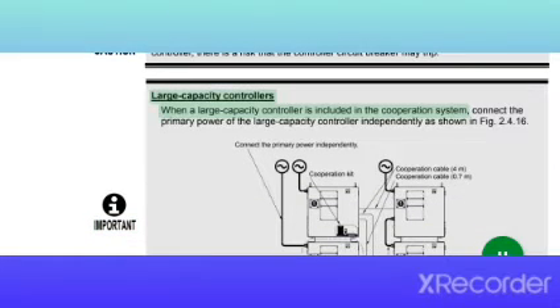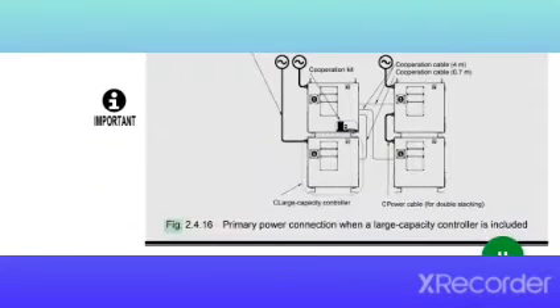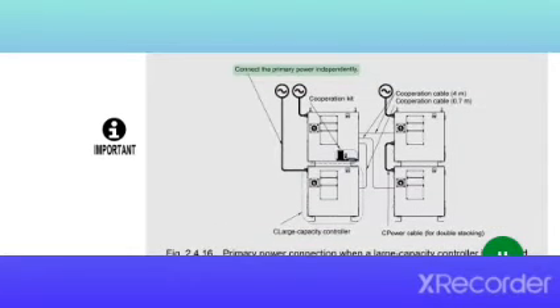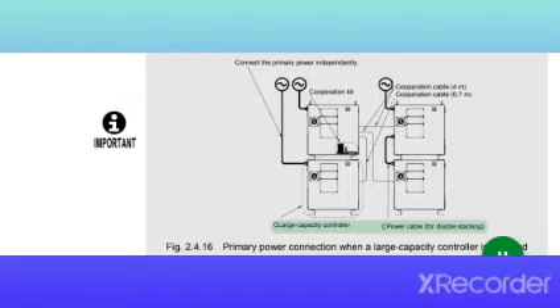Important. Large capacity controllers. When a large capacity controller is included in the cooperation system, connect the primary power of the large capacity controller independently as shown in Fig. 2.4.16. Fig. 2.4.16 Primary power connection. When a large capacity controller is included, connect the primary power independently. Cooperation kit. Cooperation cable 4 meters M. Cooperation cable 0.7 meters M. Large capacity controller C. Power cable for double stacking. 2.4 Cooperation kit connection and power on methods.